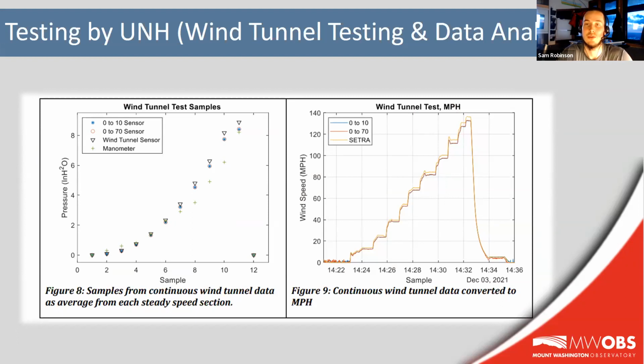And you can see that the two sensors from pitot 22, both 0 to 10 and 0 to 70, provided very similar pressure readings throughout the duration of the whole test, which was definitely a good sign. And also somewhat expected, as these wind speeds were within both of those sensors' ranges. The pressure sensor from the wind tunnel reference pitot did read slightly different pressures toward the high end of the wind speed range. But again, the trend is more or less what we were looking for, as these are all different sensors and the difference is marginal.